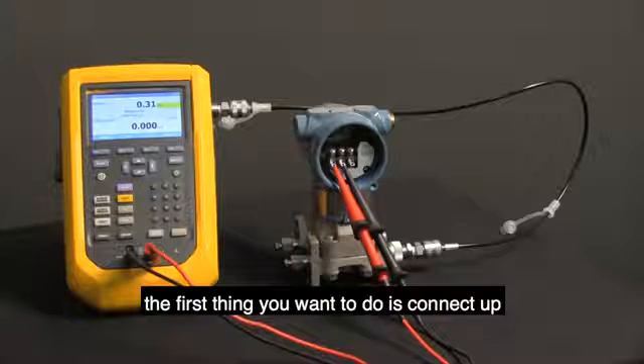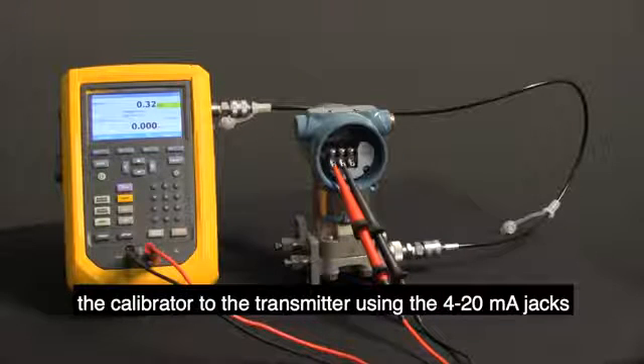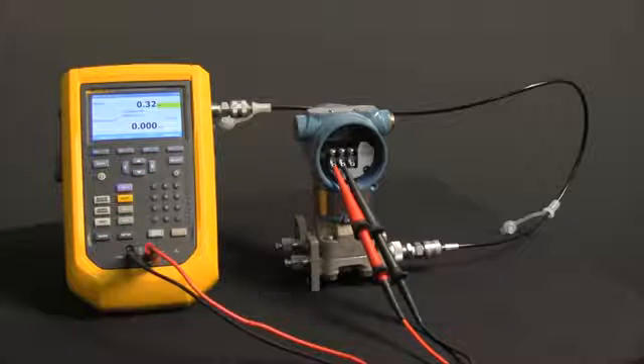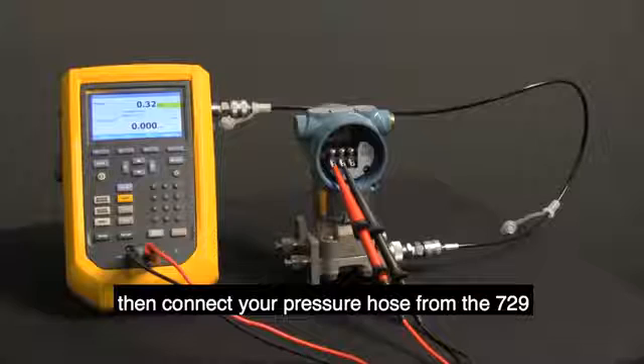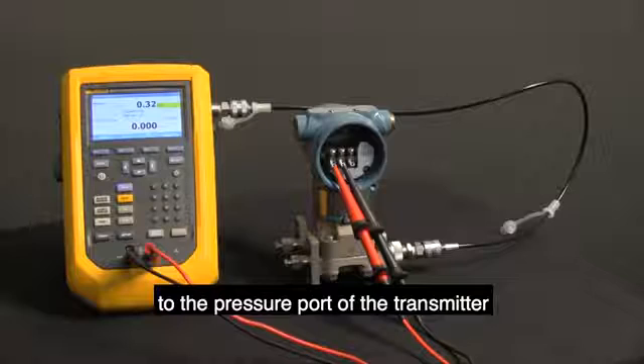The first thing you want to do is connect the calibrator to the transmitter using the 4 to 20 milliamp jacks, going to the plus and minus on the transmitter. Then connect your pressure hose from the 729 to the pressure port of the transmitter.